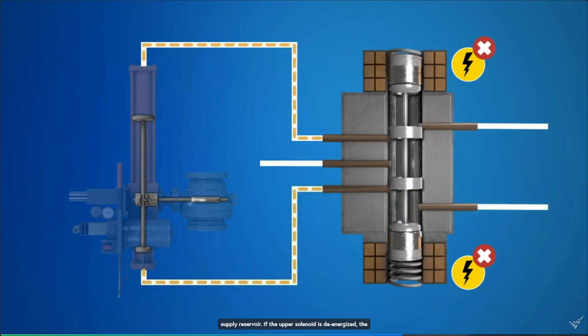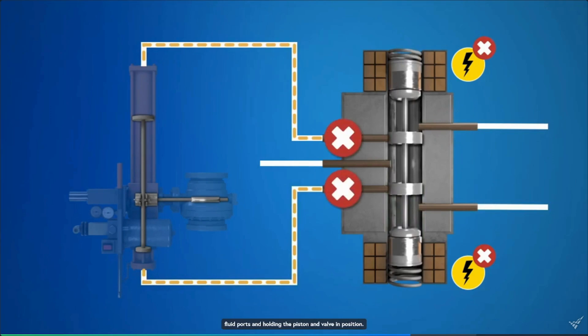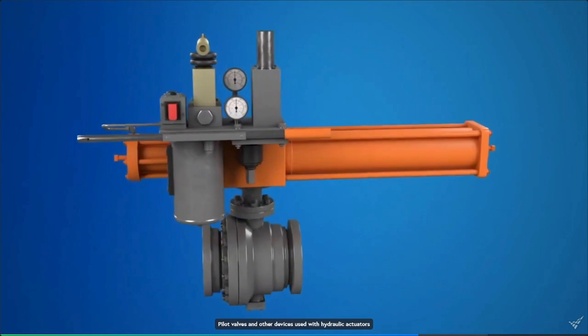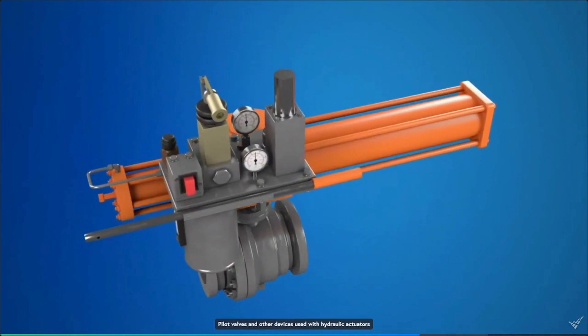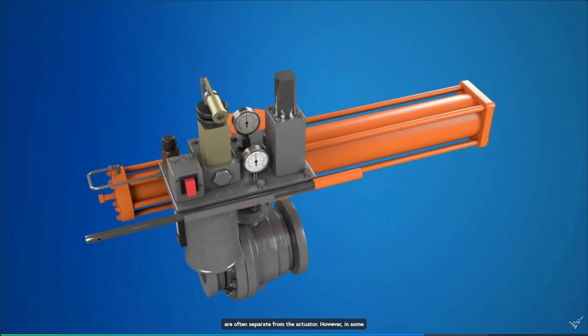If the upper solenoid is de-energized, the springs return the spool to the neutral position, blocking the fluid ports and holding the piston and valve in position. Pilot valves and other devices used with hydraulic actuators are often separate from the actuator. However, in some actuators, all the components may be part of a single unit.